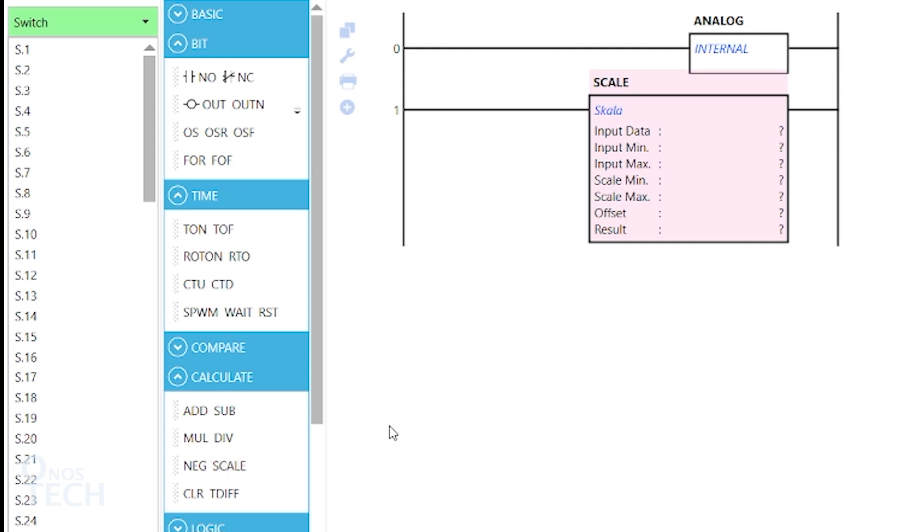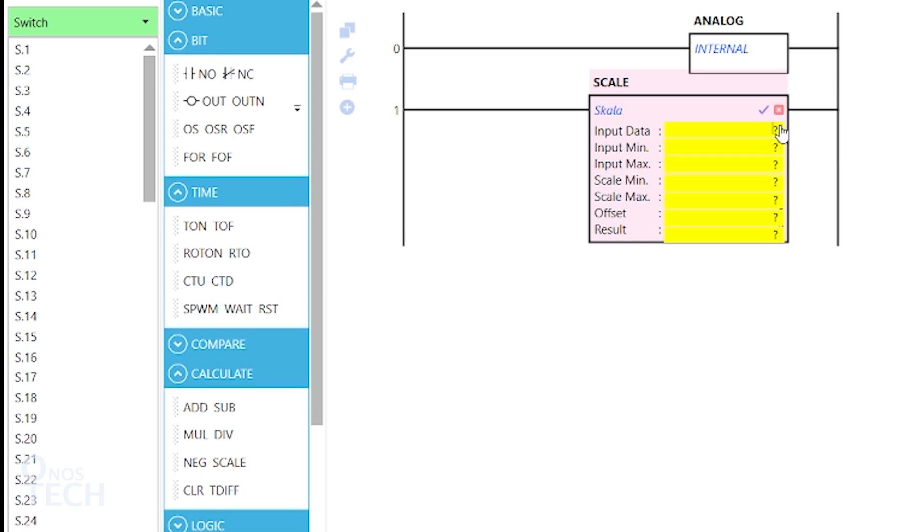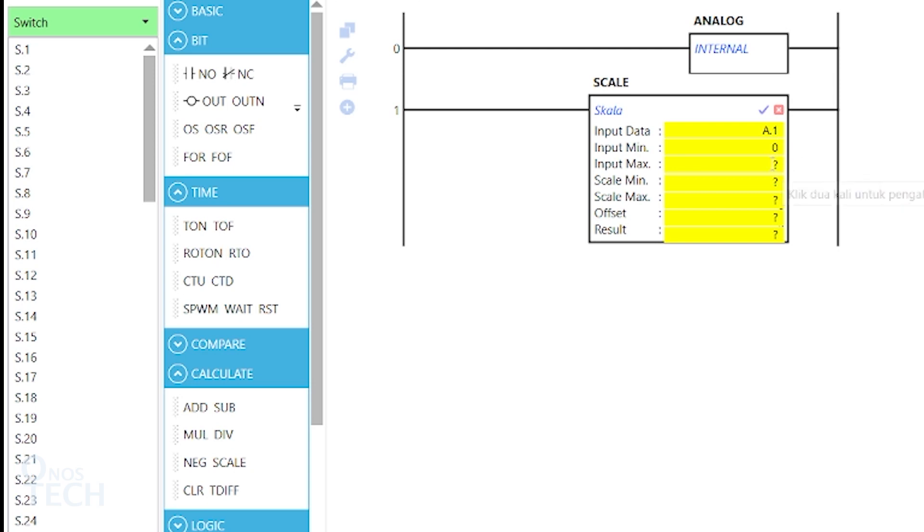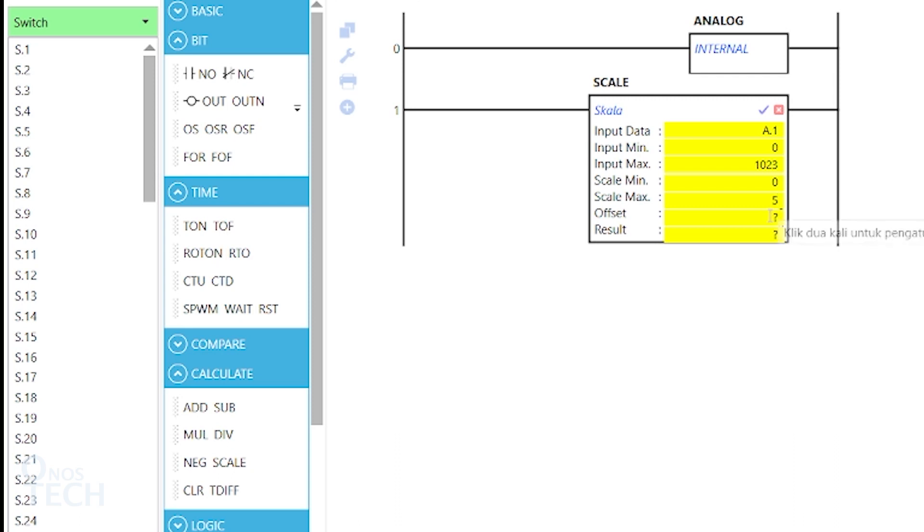The potentiometer range of measurement is 0 to 5 volts. Now, double-click on the Scale instruction and set the input data to A.1. The input minimum to 0. The input maximum to 1023. The Scale minimum to 0. The Scale maximum to 5. Offset to 0. And the result to I.1.